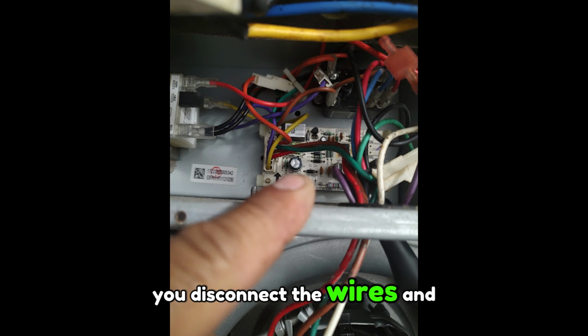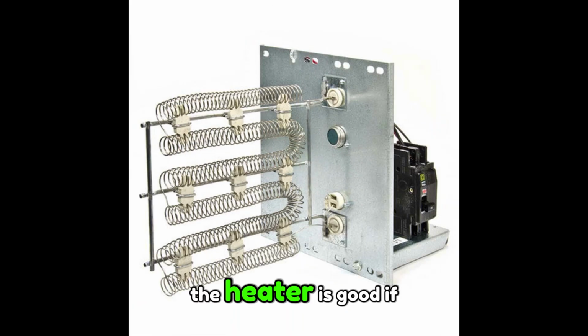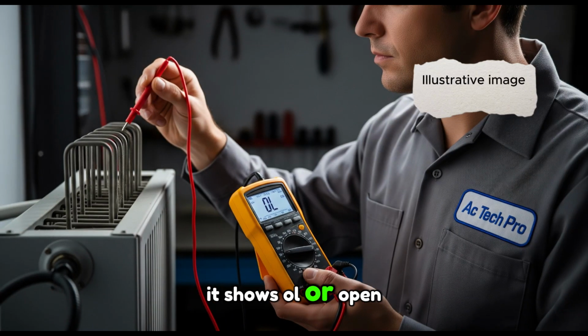You disconnect the wires and measure across the heater terminals. If your meter shows 8.2 ohms, the heater is good. If it shows OL, or open line, the heater is burned out and needs replacement.